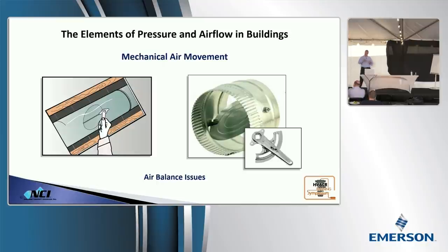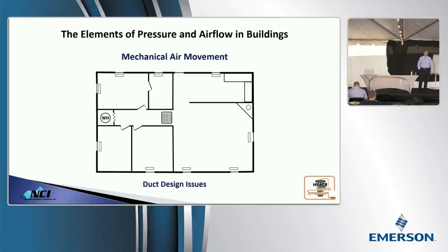And once again, these tie back down to some of the most basic airflow issues that we've talked about, because they're taking the path of least resistance, and also us being able to control it. You shut the damper off, you start to shut those conditions down. Now, what about duct design?